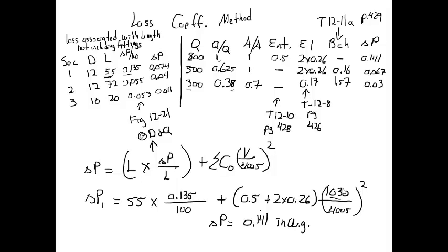Now, in your homework, you're going to end up needing to size some ducts. And the way that you size the ducts is that you just basically have to size the duct system. If you're given a network, right? If you're given a network, you need to be able to pick the size, the diameter duct for each section of your network, so that the total pressure does not exceed what's available by the fan. In this case, we're not limiting flow like we did for piping networks in terms of pressure drop, limited pressure drop because of any sort of noise. This is in terms of what's available by the fan.